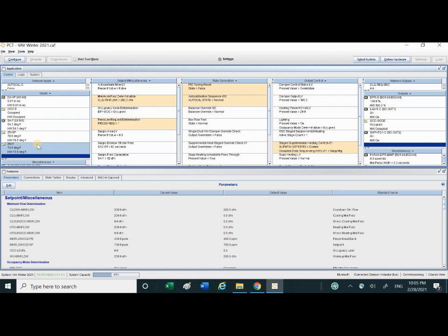Let's change the temperature set point first. Now it's 73, 75, 73, 71, looking lower. Sixty-four. So the set point is 64. Here, the thermostat set point is set to 64 Fahrenheit degrees. So it's lower than the zone temperature. So the heating is off.